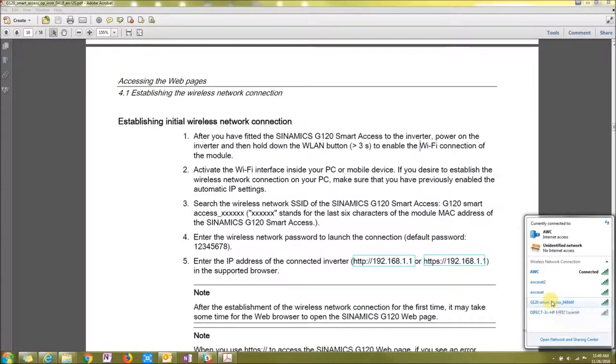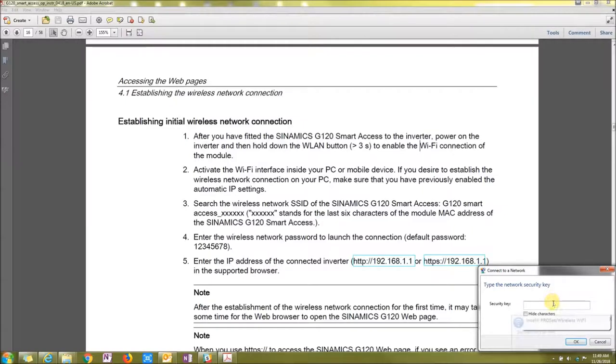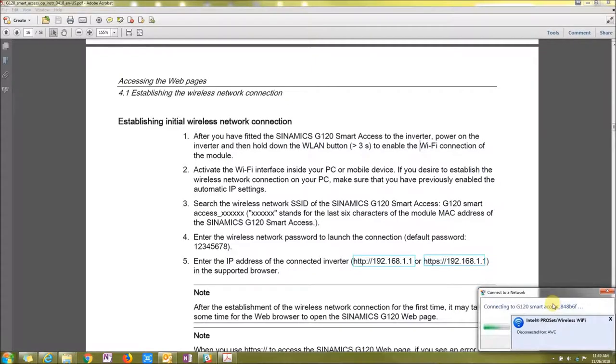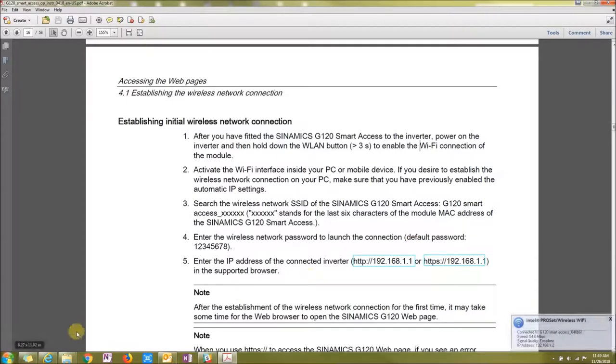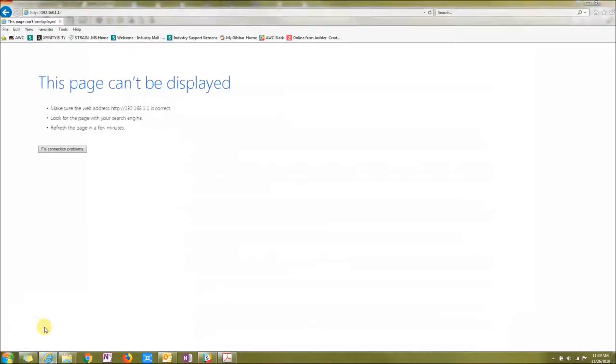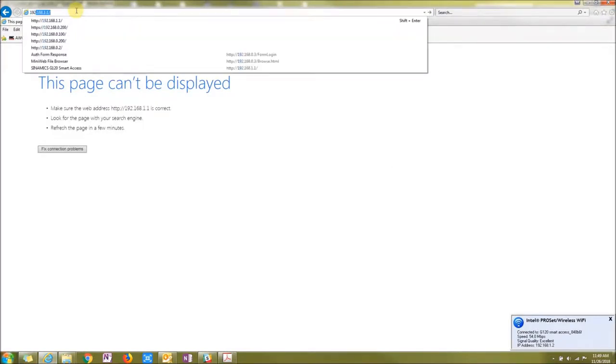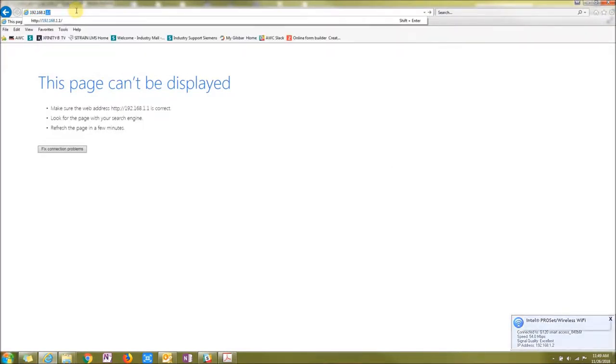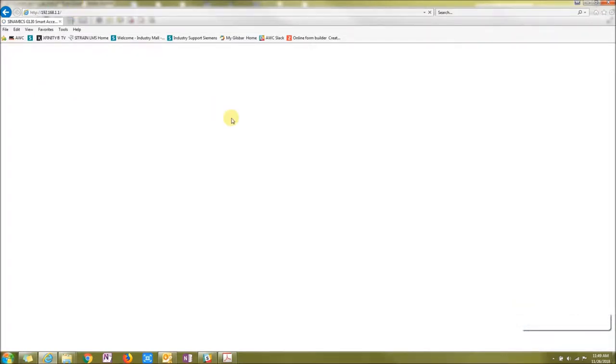It should show up with the MAC address of the module itself. You're going to click here on the G120 Smart Access, and the initial password is going to be 12345678. Once it's connected up to the unit, you're going to want to go to an internet browser and type in 192.168.1.1. That will connect you to your Smart Access.